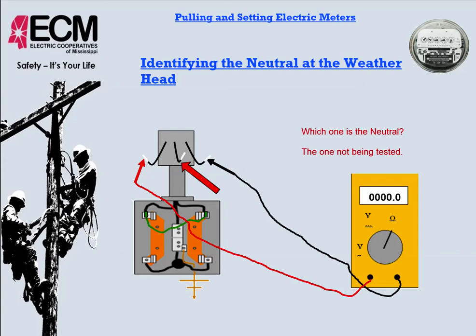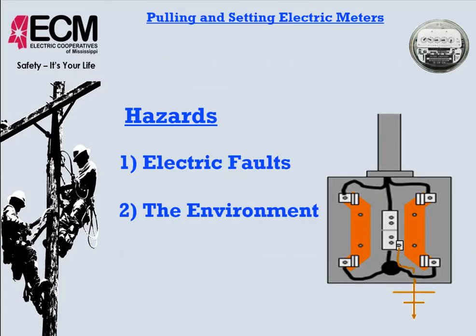So hazards, some of the things we need to think about once we have hooked up our meter base and we've made our service hot. We're getting ready to set the meter, so we need to be aware of some hazards that are involved here. One is electrical faults. Anything that's hot that touches something that's grounded, there could be an electrical arc, an electrical fault, okay? And we'll talk about fault current in just a minute and see how that could hurt us. And also we need to be aware of our environment. One could be the environment inside the meter base.